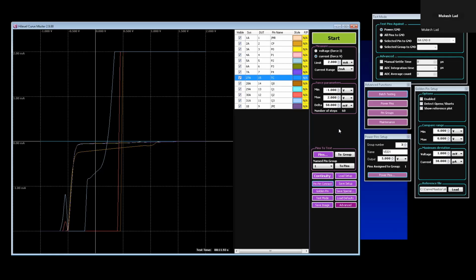And if you need more channels, because right now it's 128 channels, then 4500 is another 128 channels and an additional 4 SMUs. Customer can start with very basic and then expand easily because it's just plug and play. All you need to do is run the calibration, which is automatic, of course, and that's it. They can have a 1,000 pin system.